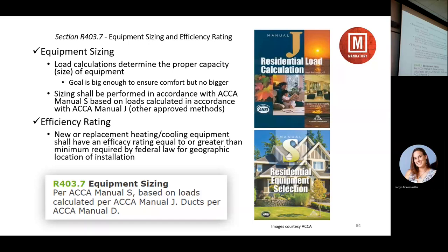So the perfect home system or commercial building system would be one where every zone has a thermostat that senses the temperature and senses as it changes a little bit, that increases the heat or decreases the heat or increases the cooling, so that we just add heat or remove heat at the exact same rate that we gain it in the summer or we lose it in the winter. Now that's the ideal system. Does that make sense? And some of these little mini splits and multi-zone mini splits, they do that. They modulate. They have inverters in them, and they ramp up and down so that you just gradually add a little bit of cooling or gradually add a little bit of heat, and they're very comfortable.